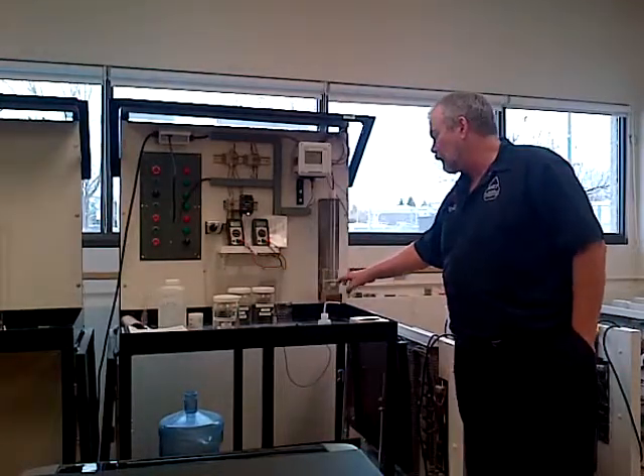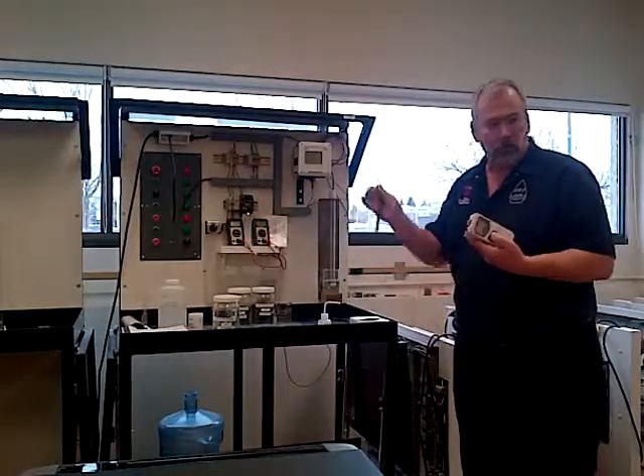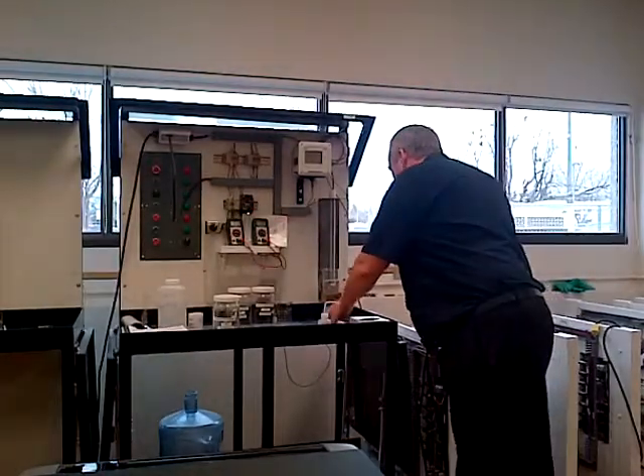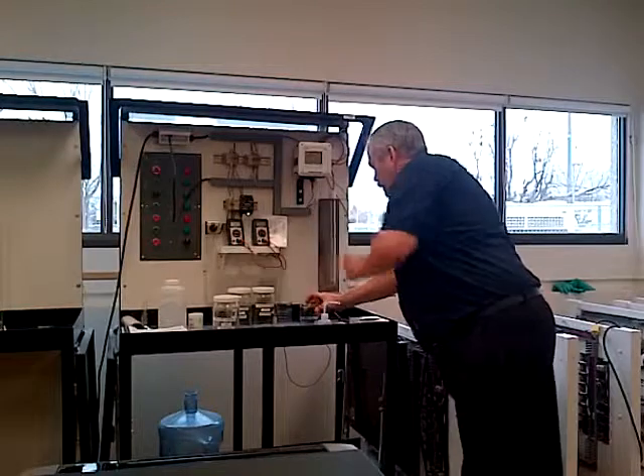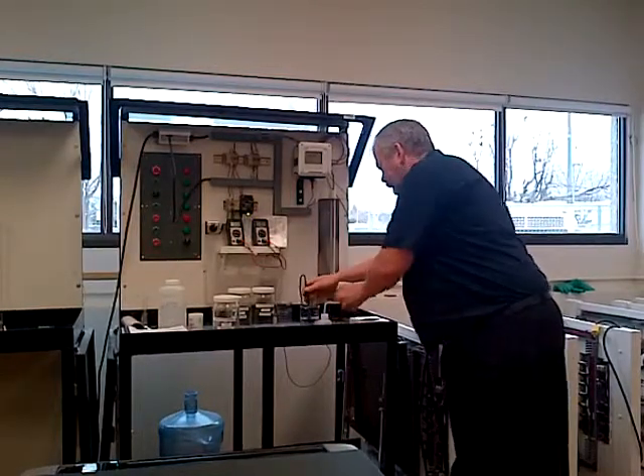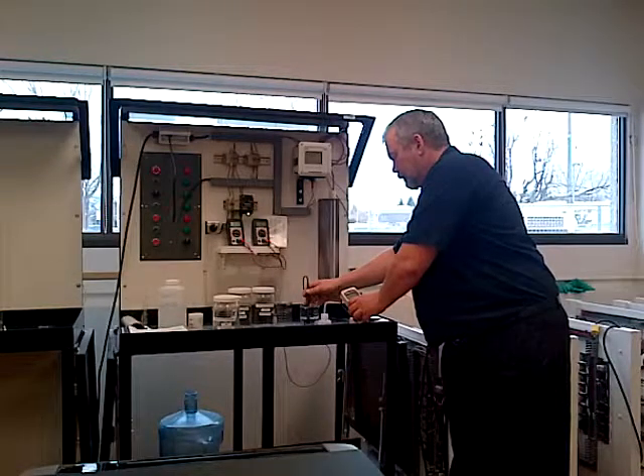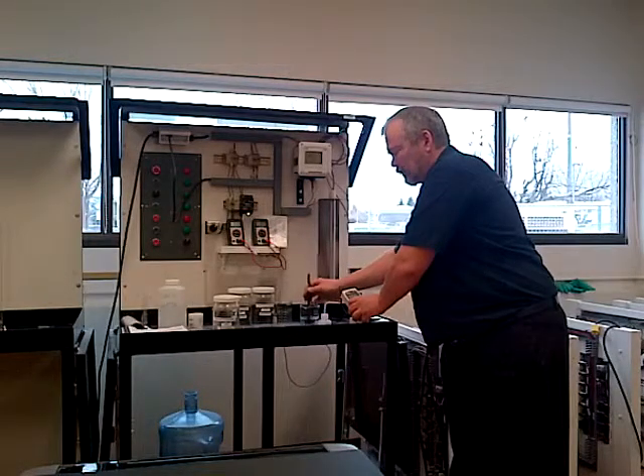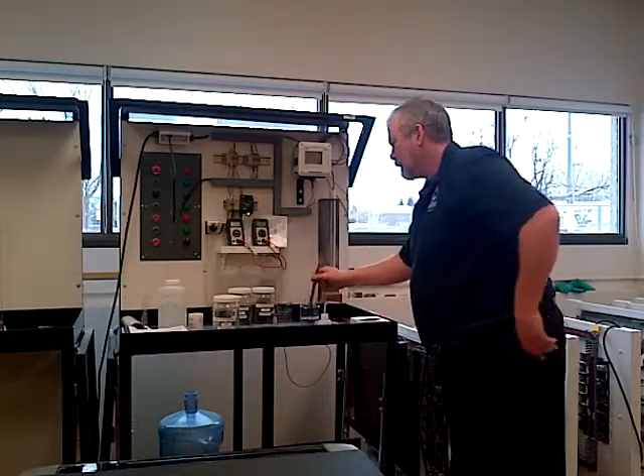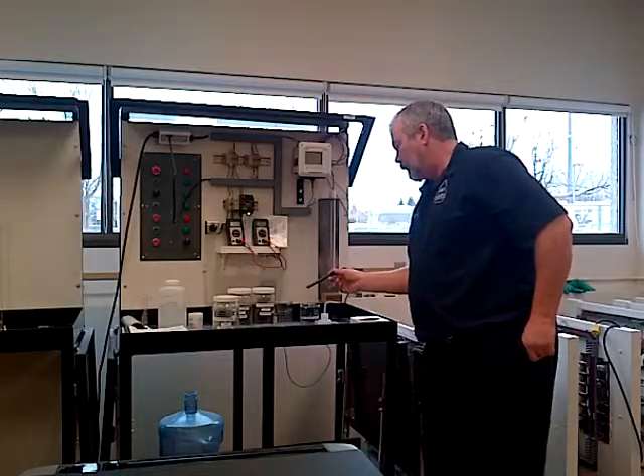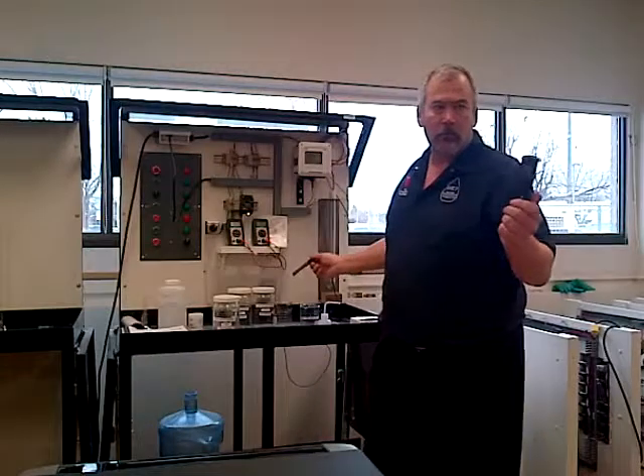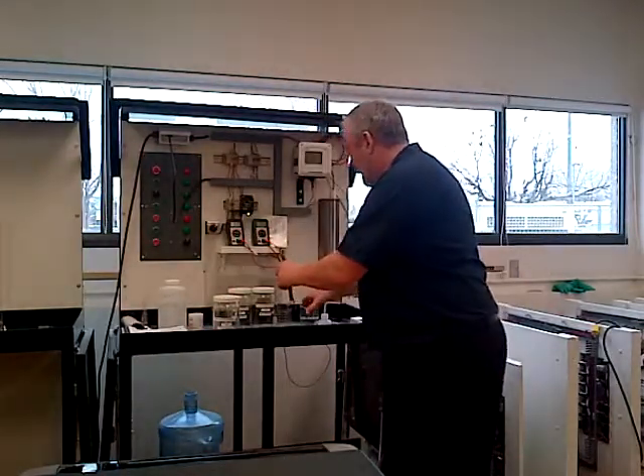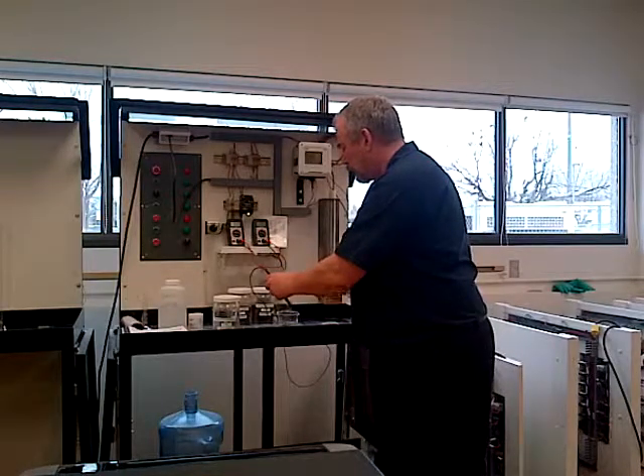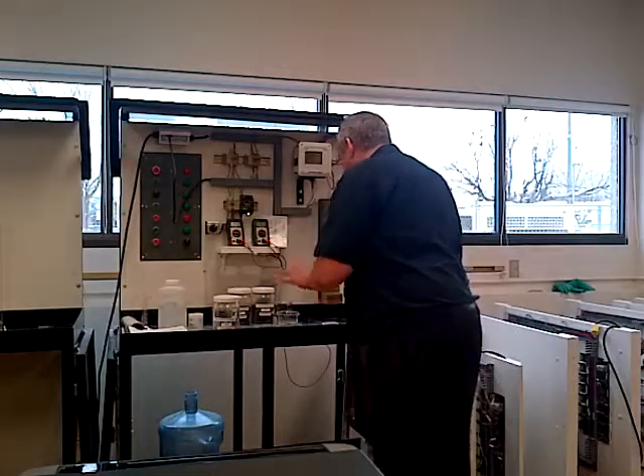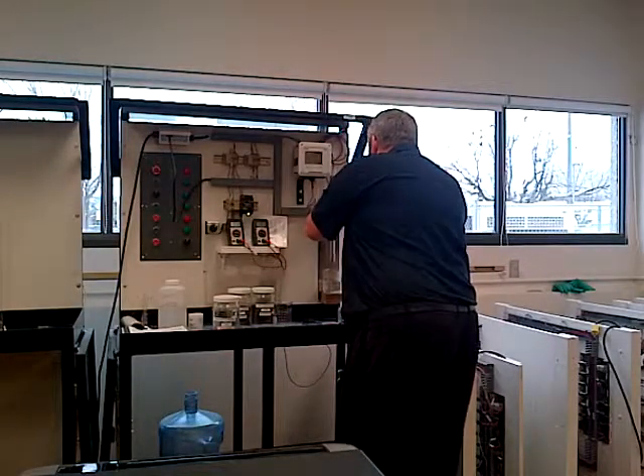You're going to measure that, then you can measure it with this little Oakton conductivity meter. And with this one, I'm getting the same. What do I have with the other one? Just a 740. Well, this one's 800 and something, 860. I just need calibration. And I may have you do it with this instrument as well. So you'll be calibrating and testing with both instruments. When you finish, please rinse off each probe, including this one. We'll take a proper file, rinse it off.